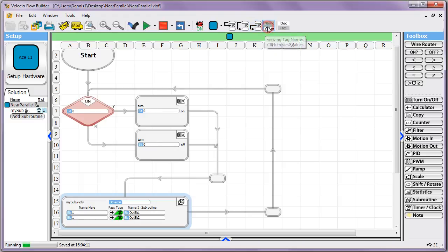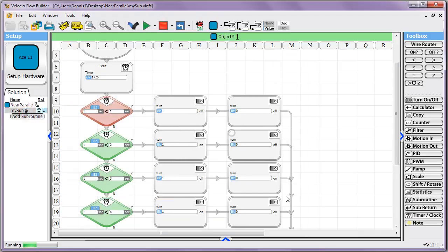So I'm turning it into debug, and I'm going to look at the values here. So I'm going to flip this switch. I've got a little simulator stick. I can flip that. You can see it turn on and off, and you can see that it is, in fact, turning on and off my output. But at the same time I'm doing this, and I'm going to keep switching it back and forth just so you know this is still going on, you can also see that the subroutine is causing these bits to go in their sequence that was described. So these two tasks are basically happening in parallel. And this shows you don't have to be stuck in a subroutine. In fact, you don't ever want to be stuck in one. You want to be getting in, doing your operation, and then immediately getting out.